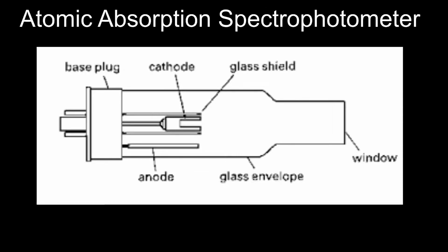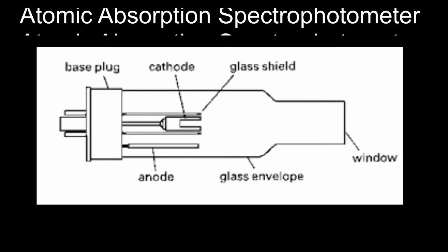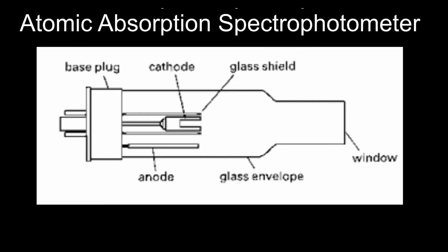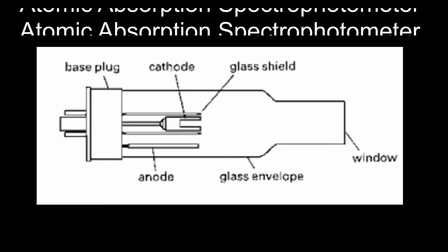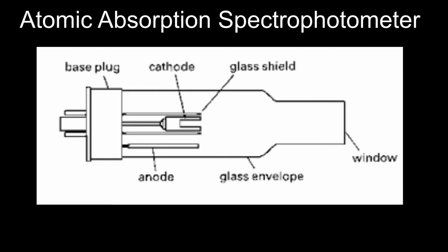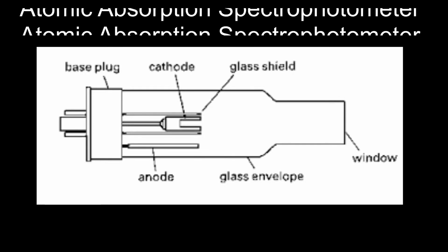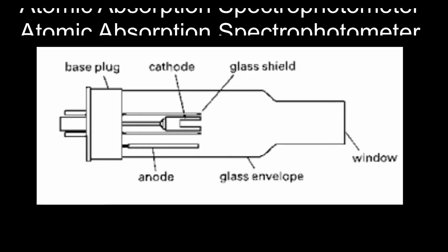These fast moving ions hit the cathode surface and remove the surface metal atoms by a process known as sputtering. These metal atoms now collide with the highly energetic gas ions and get excited. These excited metal atoms emit their characteristic radiation, which usually consists of a number of individual wavelengths. This radiation appears as a bright glow in the hollow cathode cup.